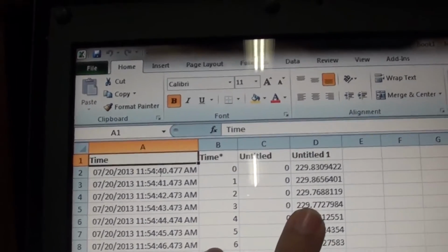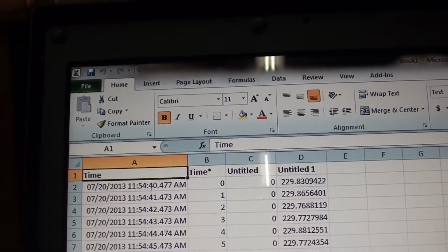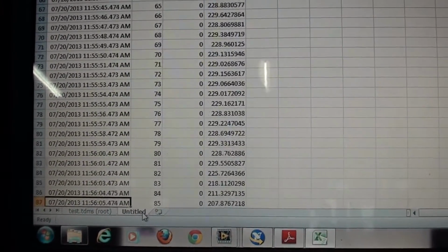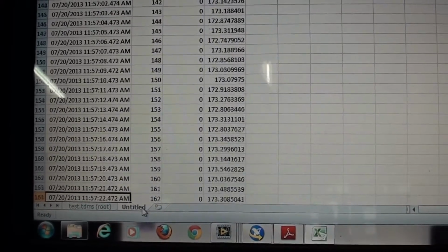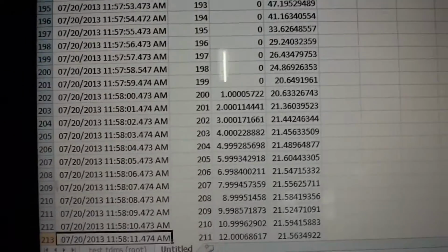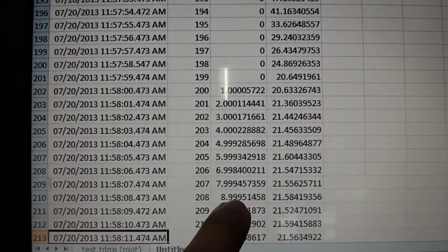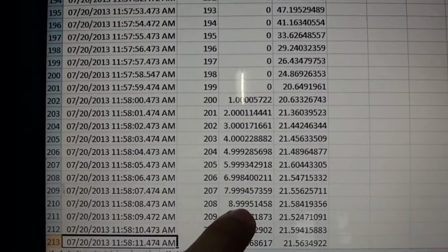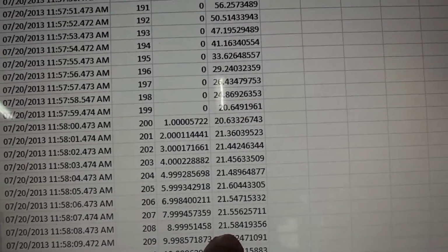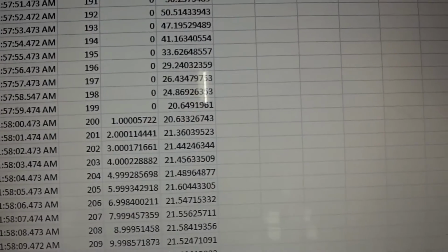And since this is not an interruption and this is actually a voltage swell, the value of the duration column is 0, as we can see here. As we go down, when we had displayed the interruption event, we are able to see the details here. At 11:58 a.m. there was an interruption that had lasted for 8 seconds. The duration of the interruption was 8 seconds, and the value of the voltage then was 21.5 volts. So this makes it clear that the value of the voltage was this at this particular instant, and the event has occurred for this much duration of time.